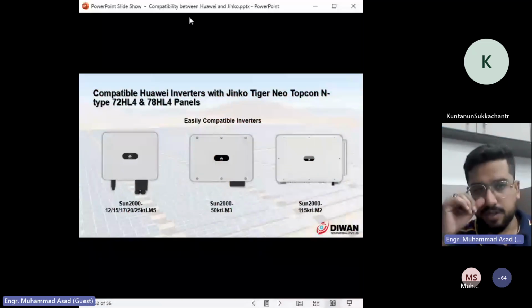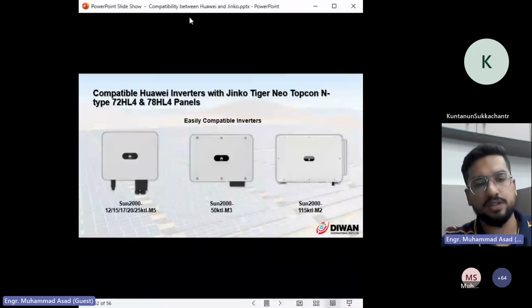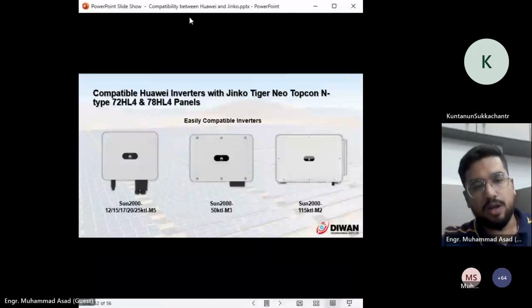Now, the compatibility of Huawei inverters with Jinko Tiger Neo TopCon N-type panels. We have 72HL4 and 78HL4 panels. The 72HL4 panels range from 560 to 585 watts, and the 78HL4 panels range from 600 to 630 watts. The Sun2000 M5 series includes 12, 15, 17, 20, and 25 KTL models, plus the Sun2000 50 KTL M3, and the larger 115 KTL M2. All are compatible with these new technology panels.